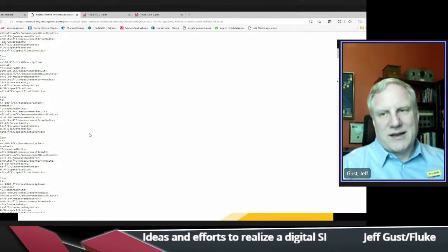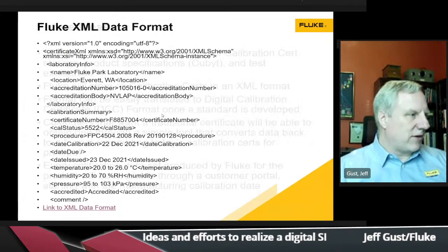So you can see test certificate results minus 100 degrees Celsius, it looks like, and the nominal value, the measurement result, the measurement result units, the error, the uncertainty, the specifications, and flags of whether it's in the specification or not. So there's a lot of information here, and it gives the end customer the ability to pull this data electronically into their system if they want, if you will, an API to convert the data and suck it into their system as well. So going back to this, yeah, fairly quick process.